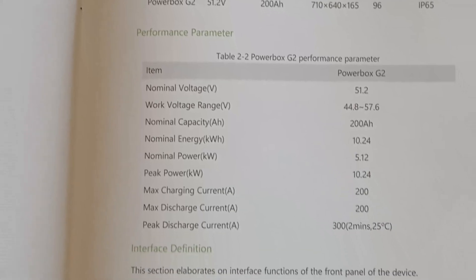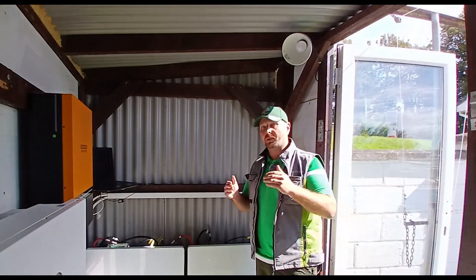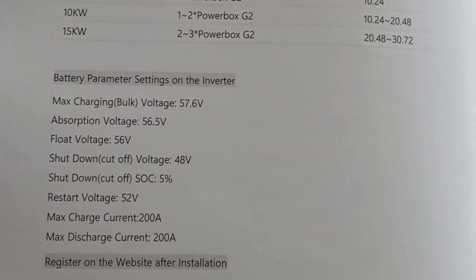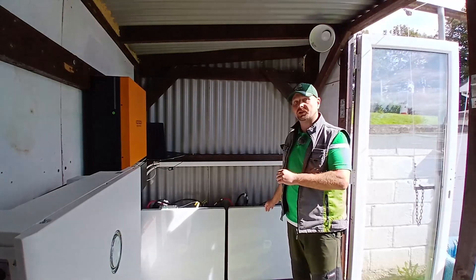The maximum charge and discharge current for these units is 200 amps, meaning they can supply a lot of power to your loads and take a lot of power back in to recharge. One thing that sets them well ahead of their competitors is their minimum state of charge, which on these is five percent — basically, 95% of the 10.24 kilowatt hours is totally usable until the system shuts down for protection.